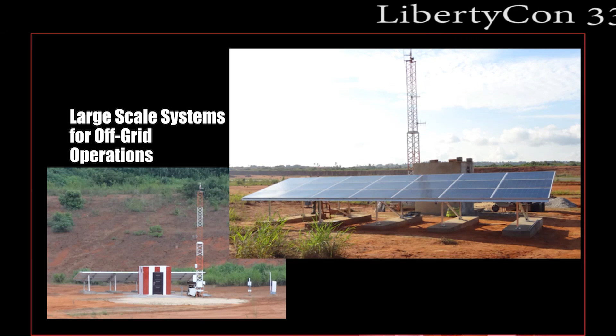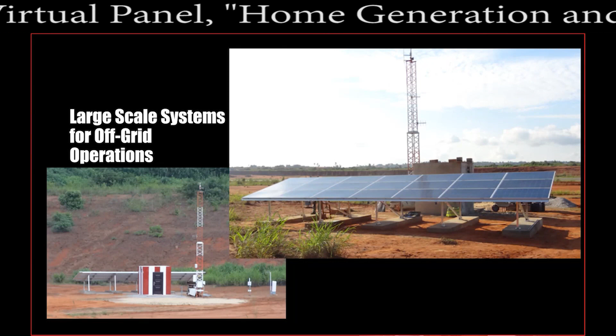The problem is that because a number of those instruments are optical, we need to keep the lenses clean, which means we need anti-condensation heaters and lens blowers. Those aren't running 24 hours a day, but when they're all on at the same time, they're pulling 3 kilowatts. So again, our biggest consumption is in heating and blowing.